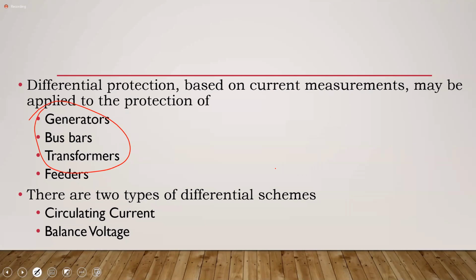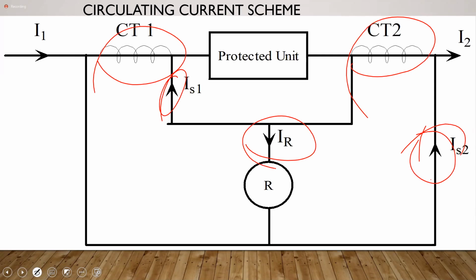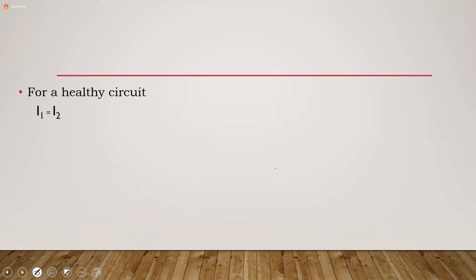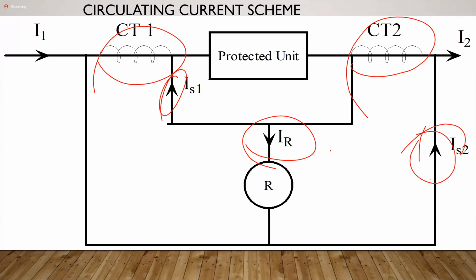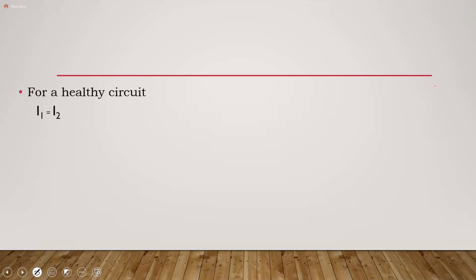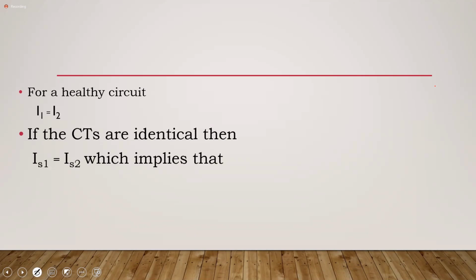All right, did you get all of this? I think I moved it a little quickly, but anyway, you can come back to the recording and get it. All right. Based on the preset value and some other considerations, it would cause the relay to operate. Okay, so just using some mathematics, nothing technical. If the circuit is healthy, it means that I1 is equal to I2. So in other words, if there's nothing wrong with what I am protecting, if the fault is outside, somewhere down the road, then whatever current is coming in would be the current leaving.